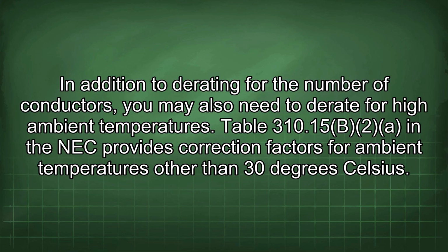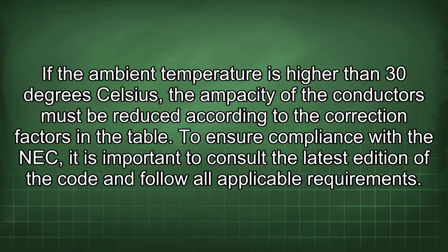In addition to derating for the number of conductors, you may also need to derate for high ambient temperatures. Table 310.15(B)(2) in the NEC provides correction factors for ambient temperatures other than 30 degrees Celsius. If the ambient temperature is higher than 30 degrees Celsius, the ampacity of the conductors must be reduced according to the correction factors in the table.